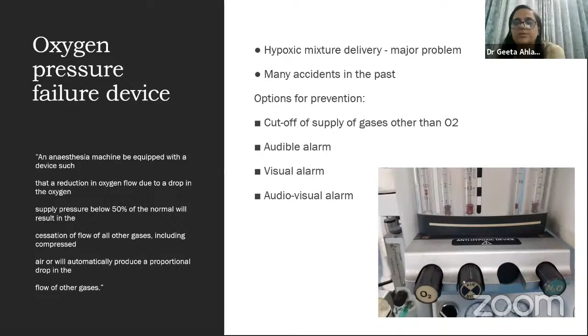The hypoxia prevention safety devices also are a part of our modern machines, like minimum mandatory flow. Just as you switch on the master switch, even if you have not opened the knob of the flow meter, a minimum mandatory oxygen flow will be seen, as is visible in this figure. This can be from 50 to 250 ml per minute, depending upon the machines.